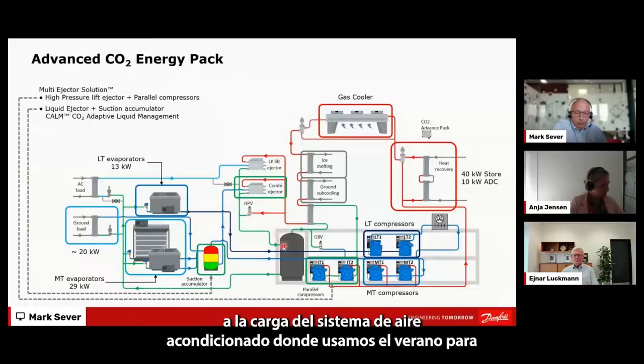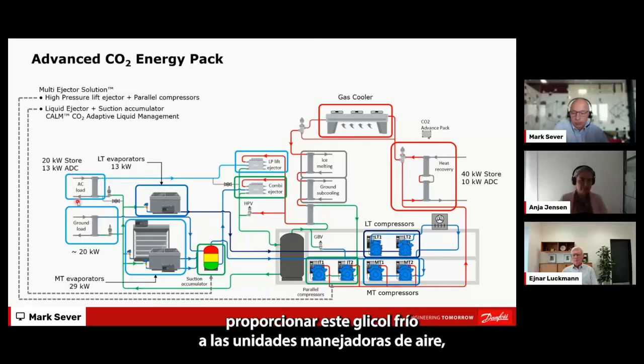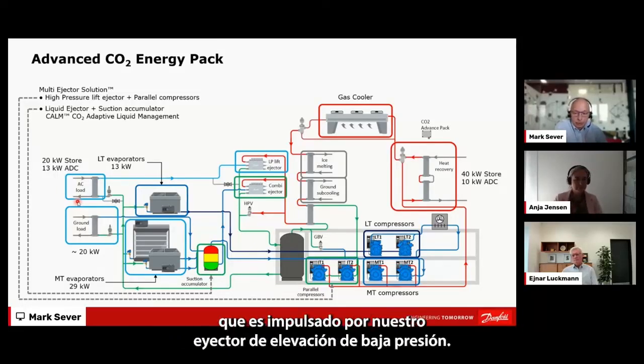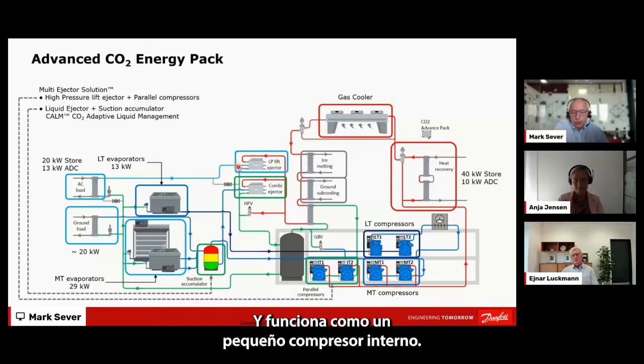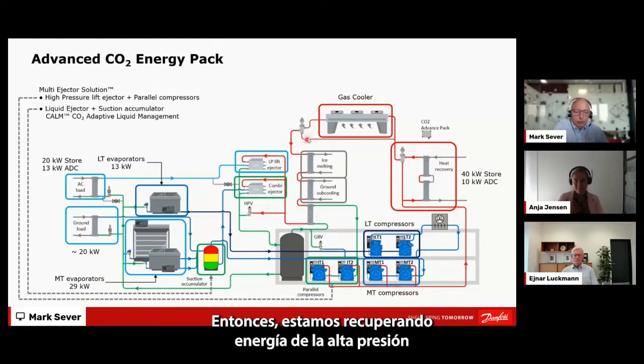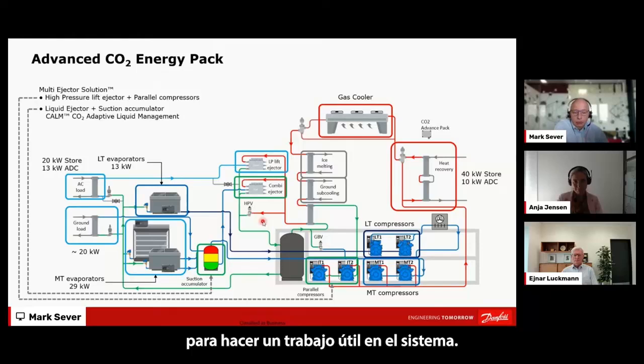All in all, we also added an air conditioning load to that system, where during summertime we have to provide glycol for the air handling units, which is driven by our low pressure lift ejector, and it works in a way like a small internal compressor. So we are recovering energy from the high pressure to do some useful work in the system.